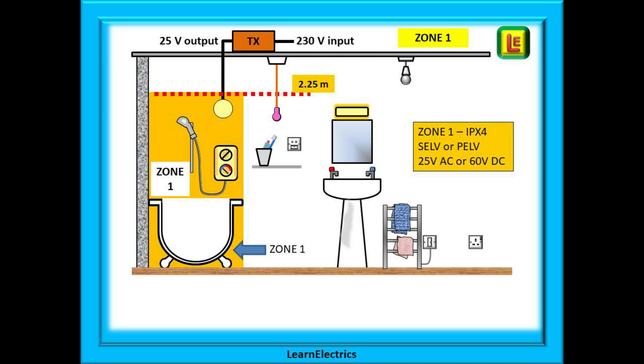If you need a refresher on extra low voltages, LearnElectrics has produced a Tech Tips video on SELV and PELV published on YouTube. Staying with Zone 1: if the bath has a barrier or panel installed that prevents access to the underside of the bath, and a tool or key is needed to remove this panel, then the underside of the bath is no longer Zone 1 — it is categorised as being outside the zones.